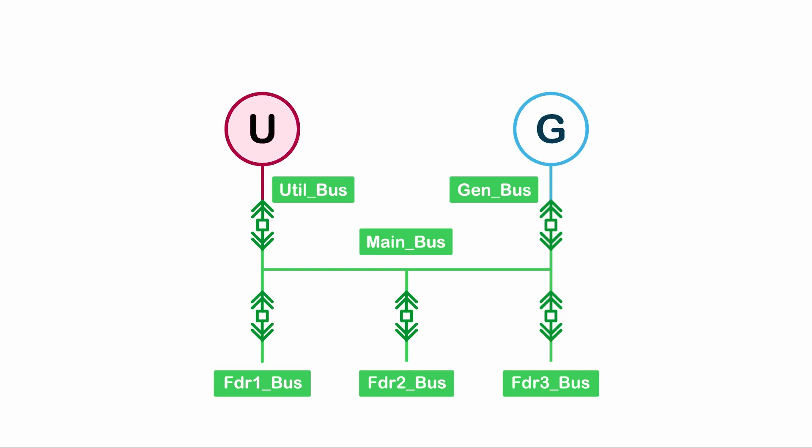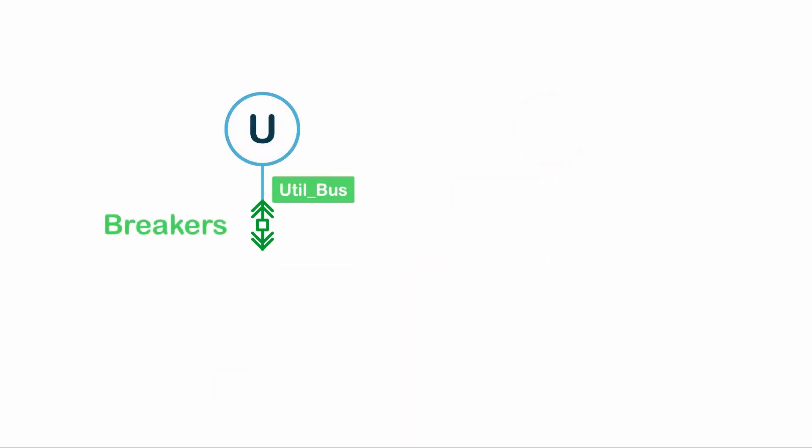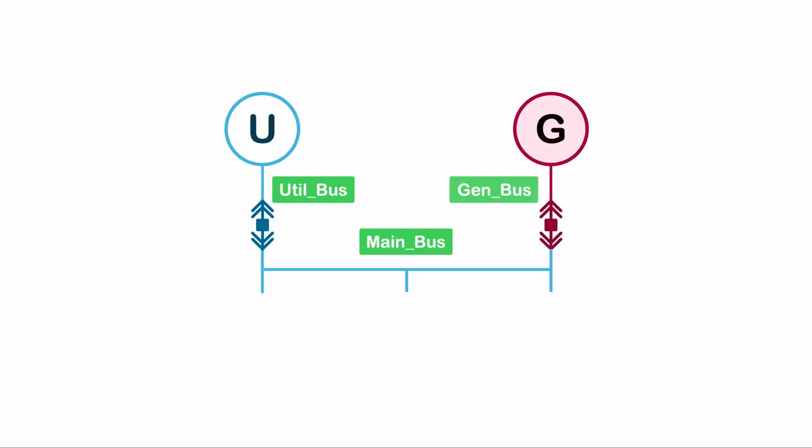If sources energize the buses they are attached to, breakers connect and disconnect buses with different names. When the breaker status is active, the breaker will pass the energized status from the bus on one side to the other. If a bus is energized by multiple sources, we can also set another color to indicate they are multi-sourced.